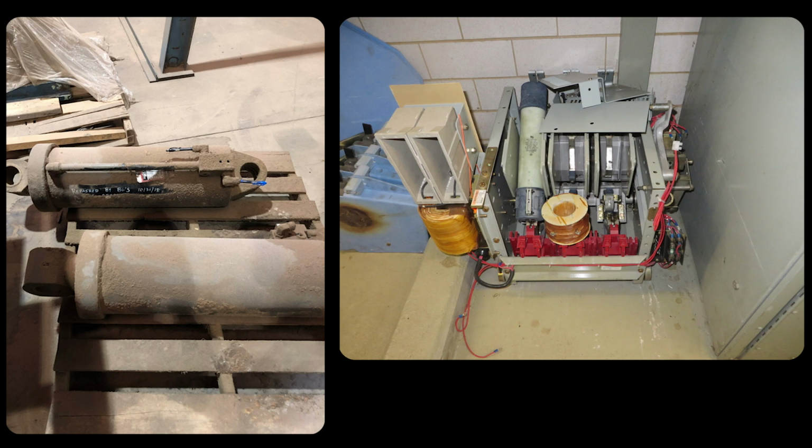Another one is the storage of spare parts. In this case, especially a rebuild part or bulky part that you store maybe out in an open area. In this case, we have some big hydraulic cylinders. They're sitting out there, they're being rebuilt. There's no caps on the oil inlet and outlet. So you're getting dust in there, and that's not what you want in a hydraulic system where you have tolerance of 5 microns or better.